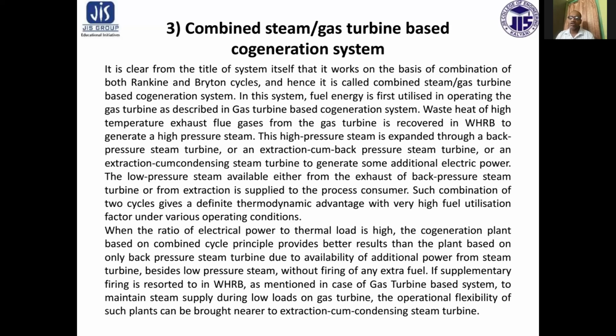Such a combination of two cycles gives a definite thermodynamic advantage with a very high fuel utilization factor under various operating conditions. When the ratio of electric power to thermal load is high, the cogeneration plant based on the combined cycle principle provides better results than the plant based on only a back pressure steam turbine, due to availability of additional power from the steam turbine besides low pressure steam.